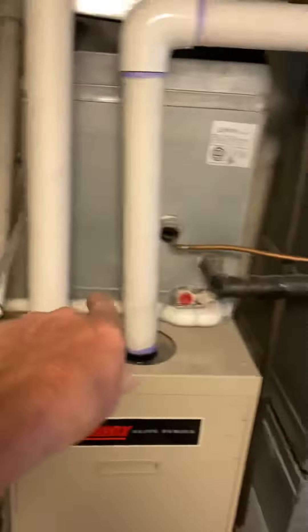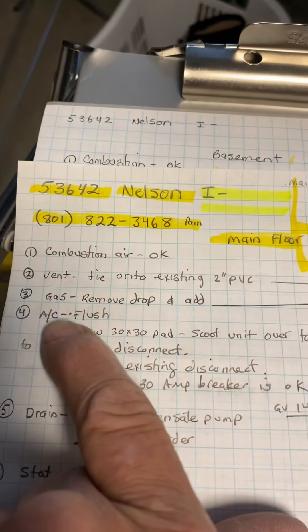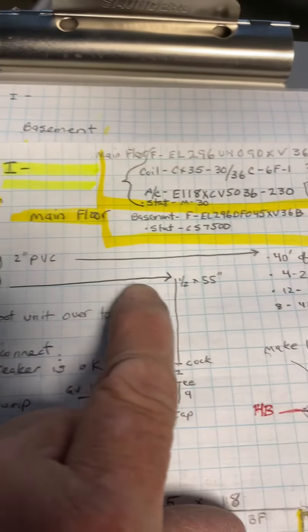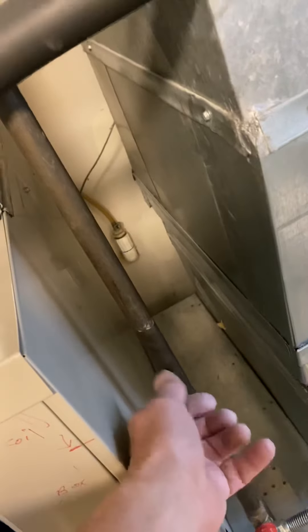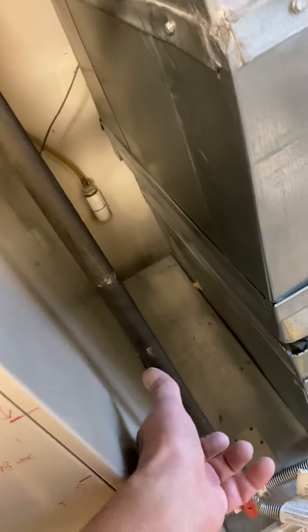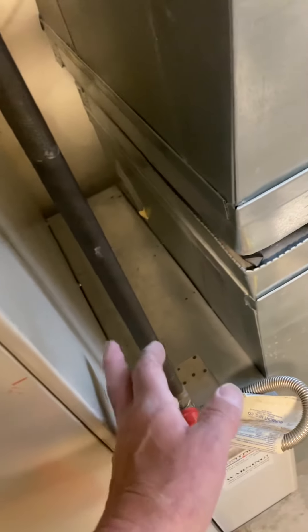The vent you're going to tie into the existing three inch PVC. Sorry, existing two inch PVC. The gas, on this one you're going to remove the drop and add a shorter drop, 55 inch drop with a gas cock and a drip leg.